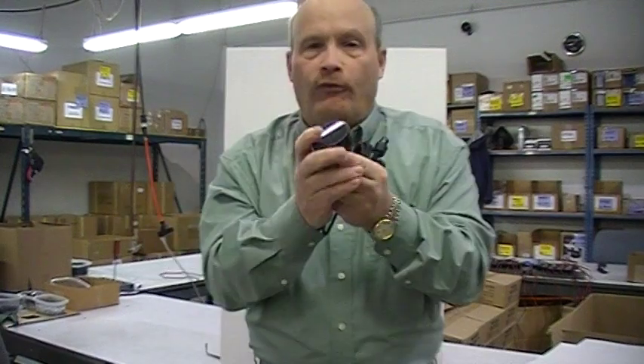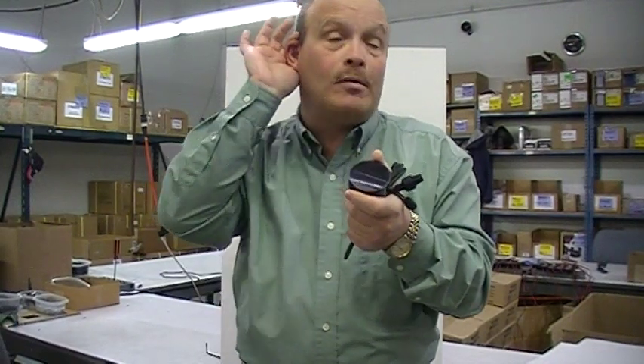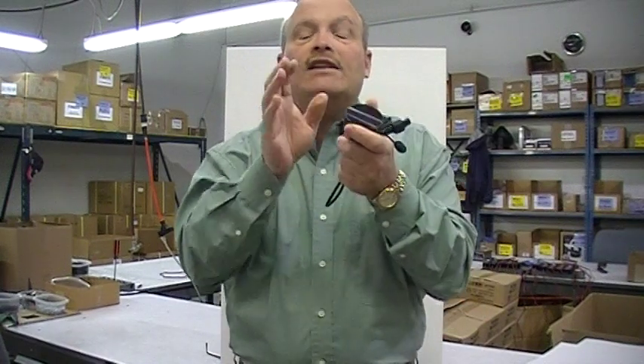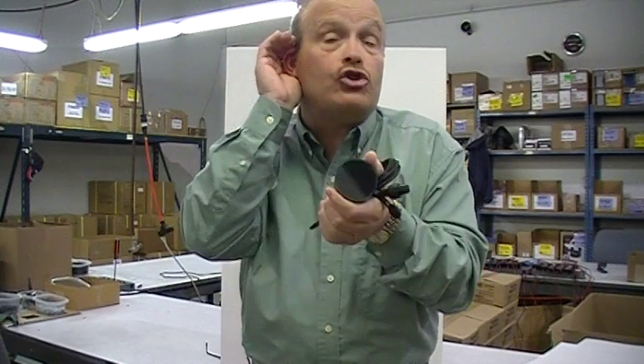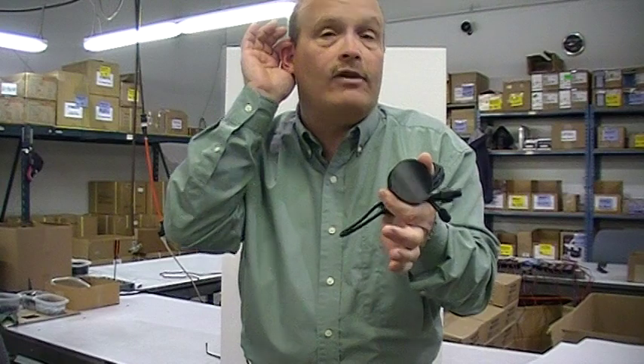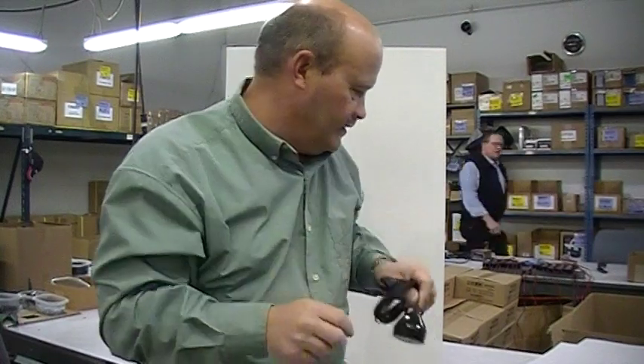So the ProView Ducer is a large crystal which gives you the maximum amount of control, which basically means the gain switch does not control power of your unit. Your gain switch simply controls how much you're allowing the transducer to receive. So if your gain is set very low, it's very focused and targeted right directly to you. As you turn up your gain, you're basically widening the area that you can hear around you. Remember, your transducer is sending out a ping that floods the entire water column. But by adjusting the gain, you control what you hear with the gain switch. That's what the ProView does.